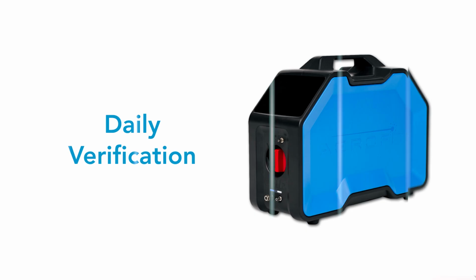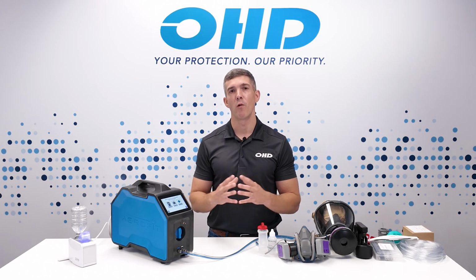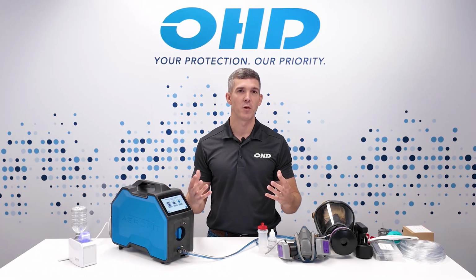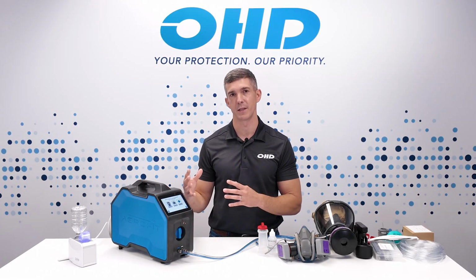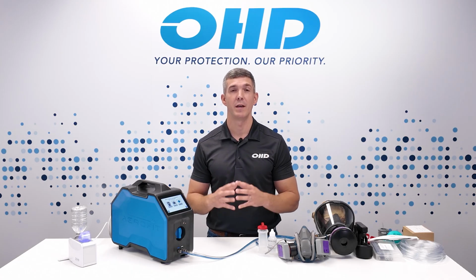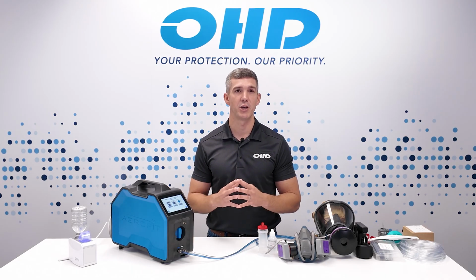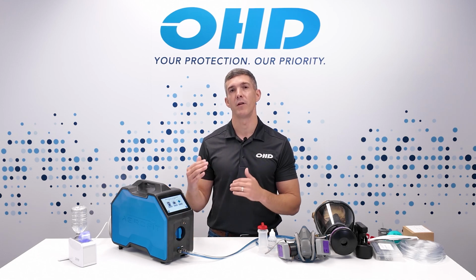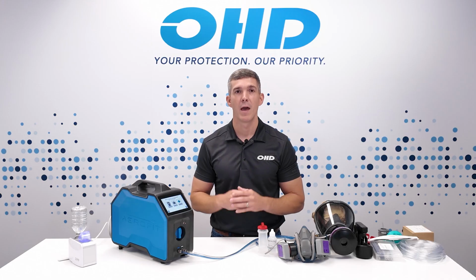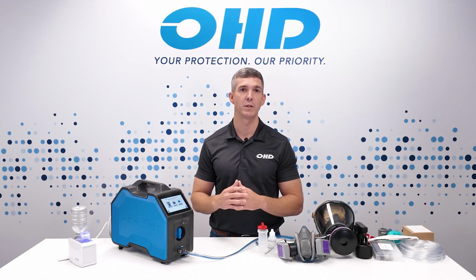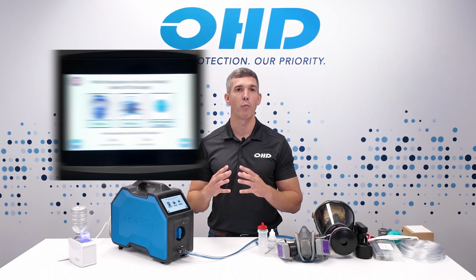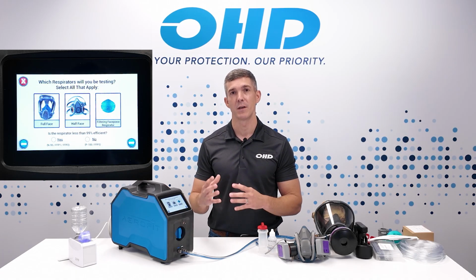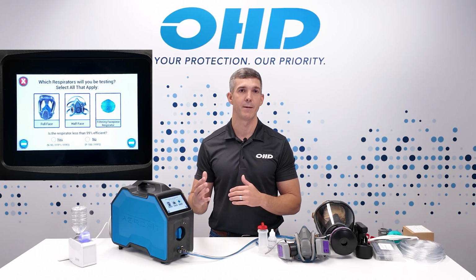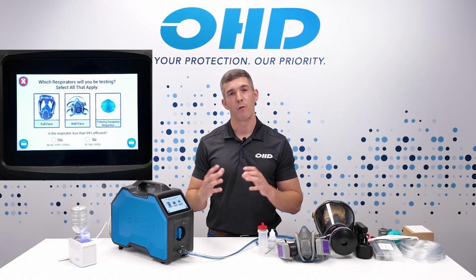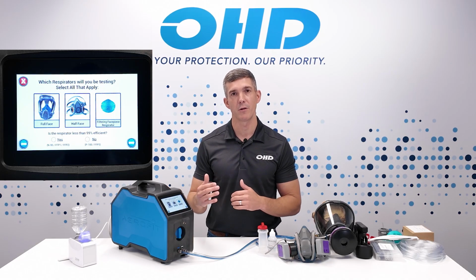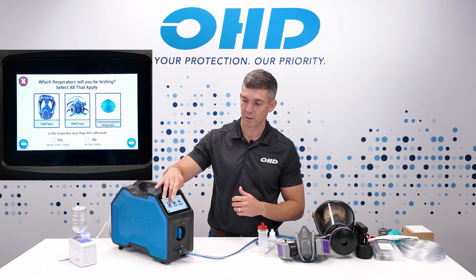A daily verification is a series of tests or measurements performed on both the instrument and the environment to ensure that they are suitable for fit testing. Daily verification will be recommended at the beginning of each day and can also be initiated at any time through the green daily verification icon on the home screen. After prompts to connect your tube assembly and insert your wick assembly, the AeroFit will prompt you to select the type or types of respirators you will be testing that day. You can choose more than one, for example, both full-face elastomeric respirators and filtering facepiece respirators.